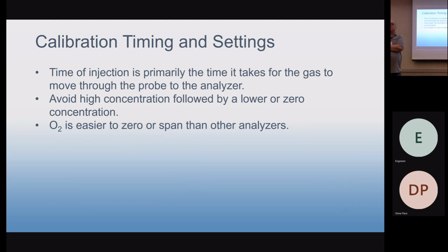Yeah, there's problems with that too, and I wanted to speak about it later. But you're right. The problem with the high concentration followed by the low concentration is the CO analyzers and the NOx analyzers seem to want to hang on to that gas. And so getting your zero after you put in a high concentration of CO on your CO analyzer is a lot harder than just starting with where you were with the stack and going to zero.